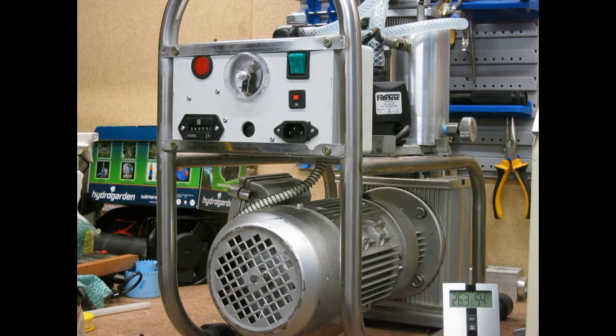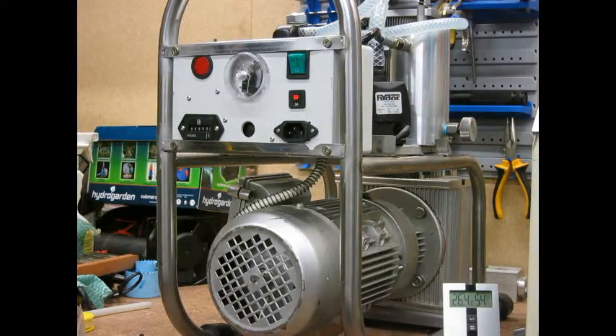Once again, same setup for the control, because we do the control box, and same setup for safety, fuse and rupture disc. But the rupture disc of that unit is proprietary, so you really should be careful not to blow it, because you will have some fun time trying to find a replacement.